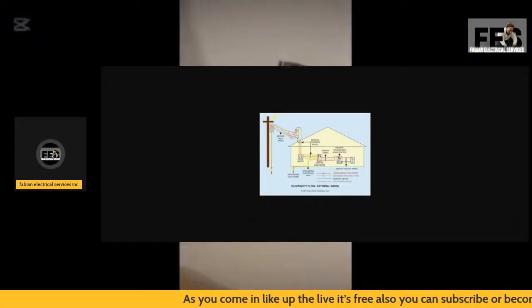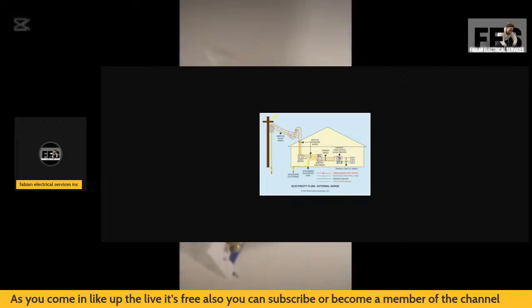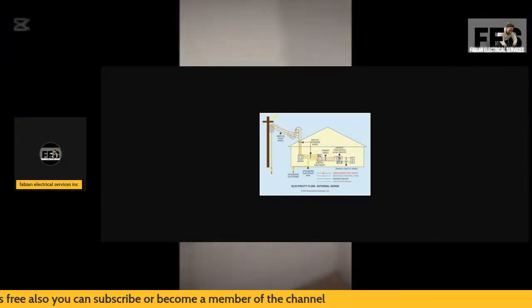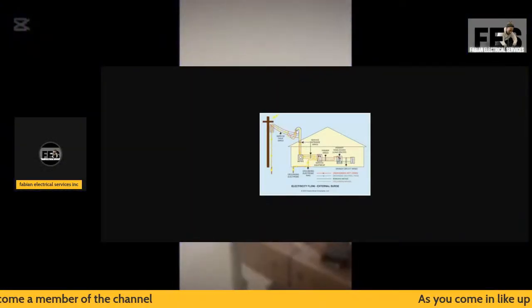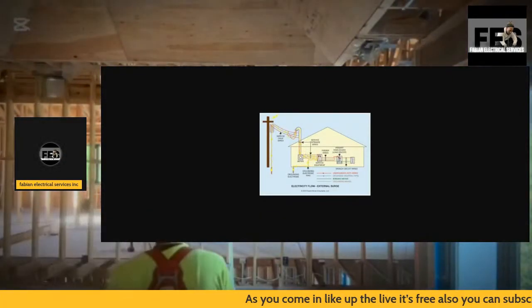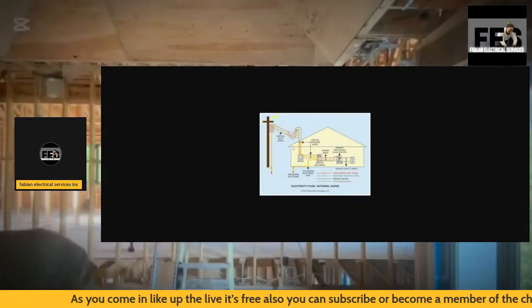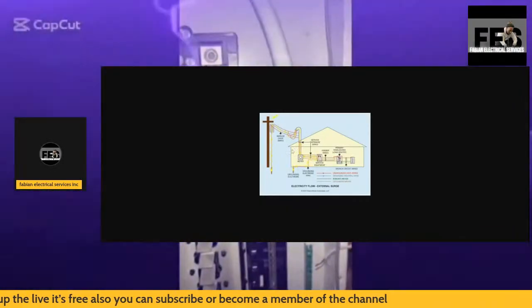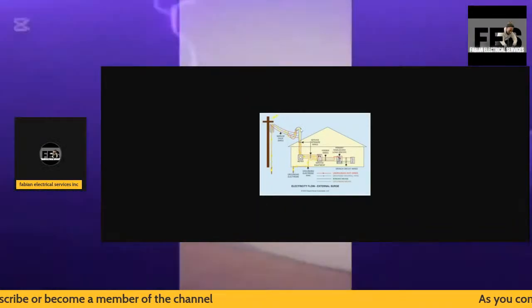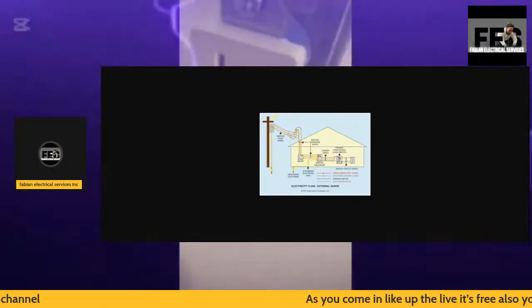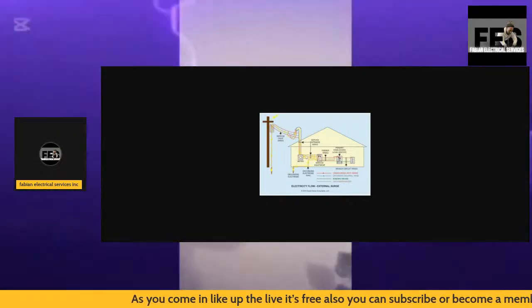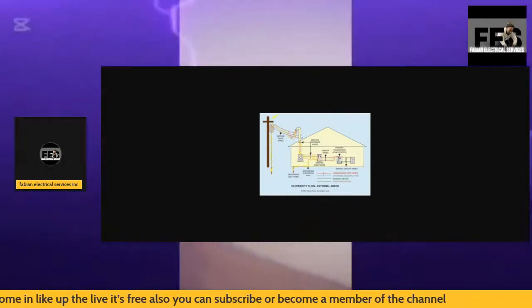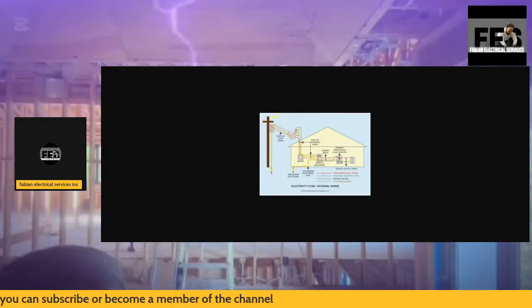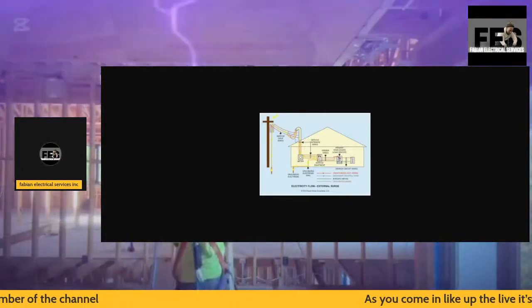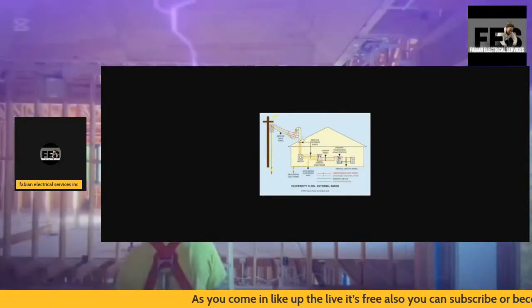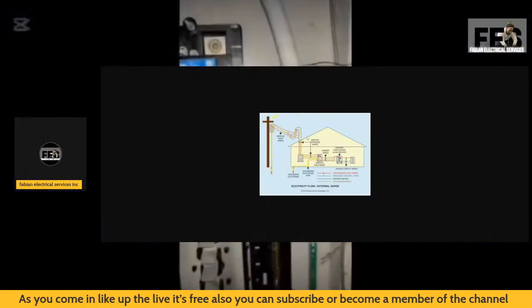A lot of times, depending on the home, if the service goes through the roof, you need to do a lot more work than if it comes from the side of the home and the service head turns before it goes into the roof. That work is easier, just straight PVC. When this type of work is involved, you need rigid conduit, this pipe here, which goes up and out with the flange and the mast and so on, when it's an overhead system.